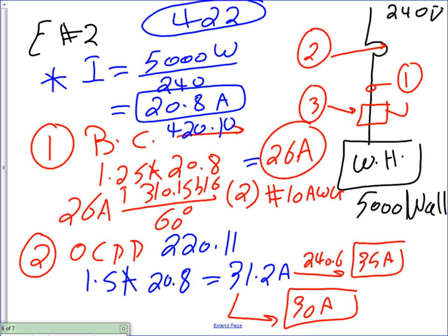And if I go to 30 amps, would the 30 amps allow me to protect number 10? Yes. Am I good to go? Yes. I can't emphasize it enough. Two options there. Option number 1, either you go by the code and go to 35, then go back and change this conductor to what? Number 8, because number 10 is a small conductor. You can't protect it for more than 30. The option that I would use is I would go down to 30 amps, because you can always go down.